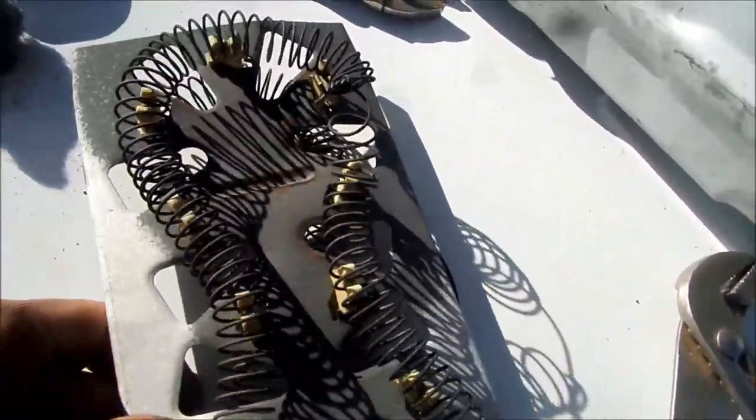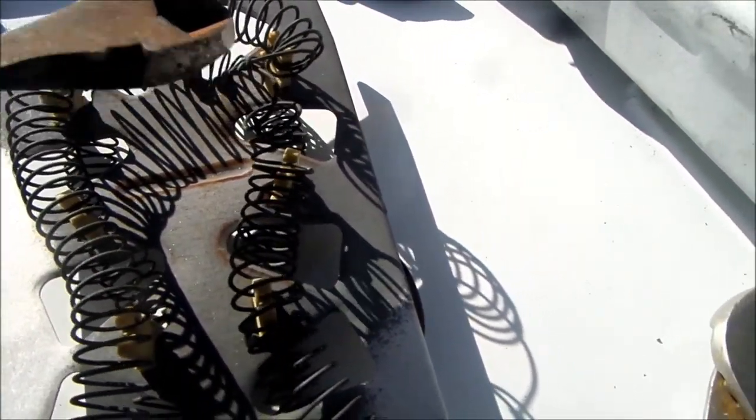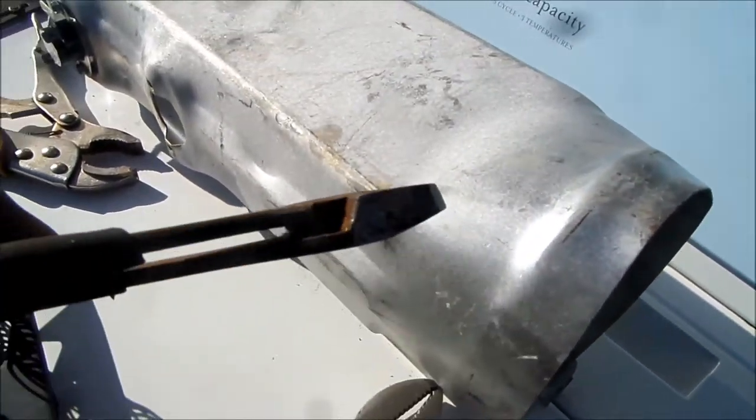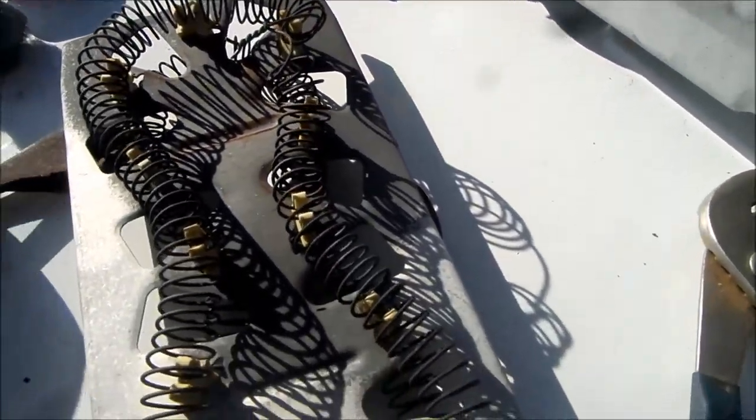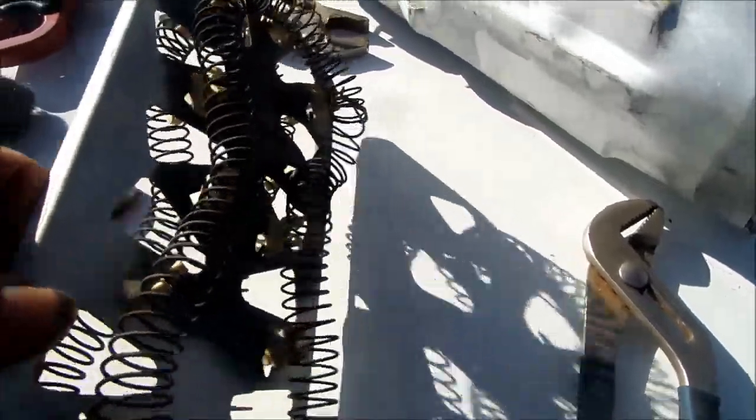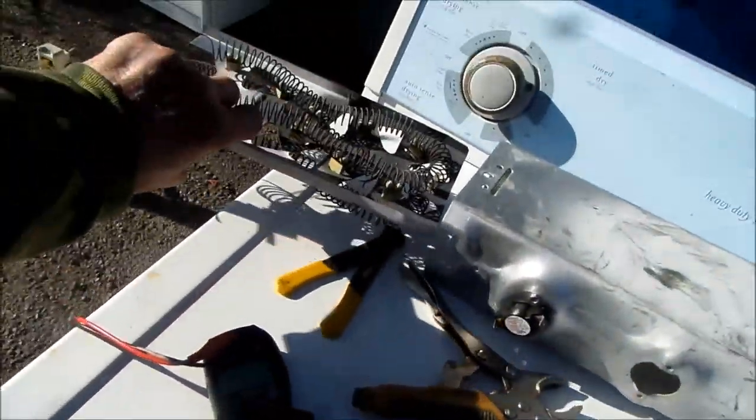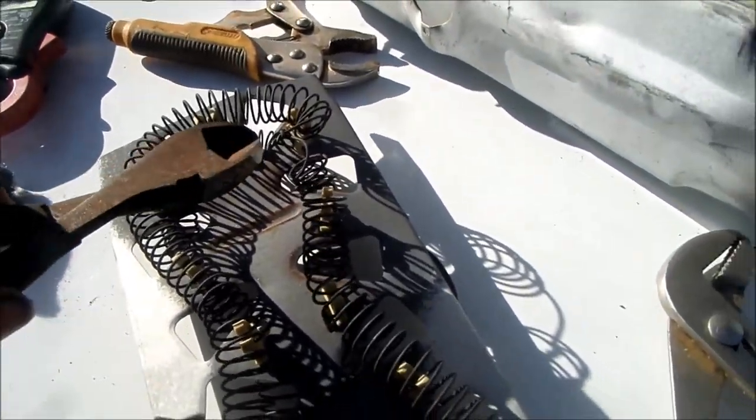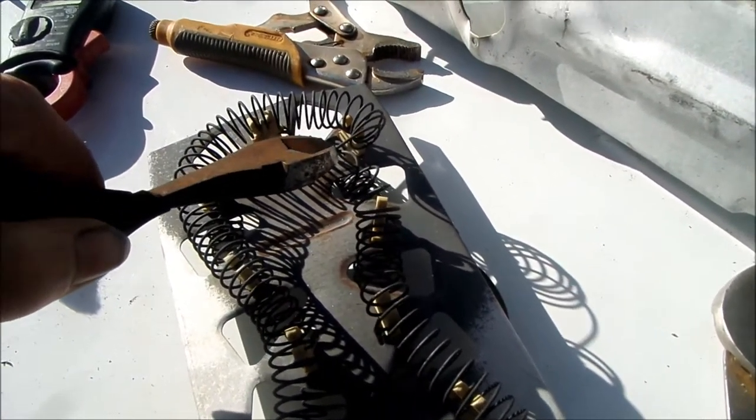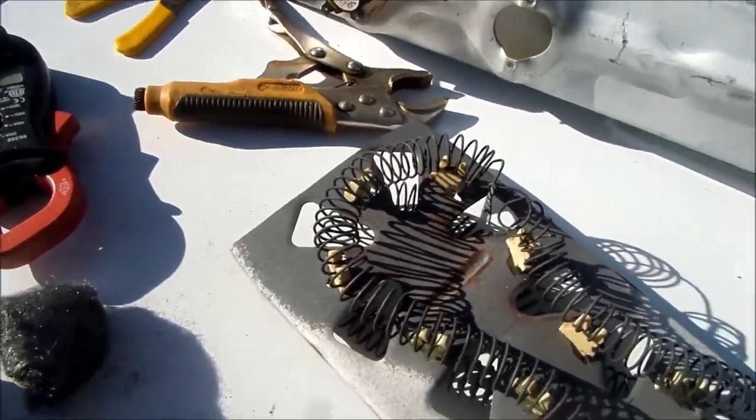And then always make sure that this area here is not protruding up, that might ground out on the heat element housing. So if I put the heat element back in, we want to make sure that this doesn't touch the ground, otherwise we'll have a short. And that could be hazardous to everyone's health.